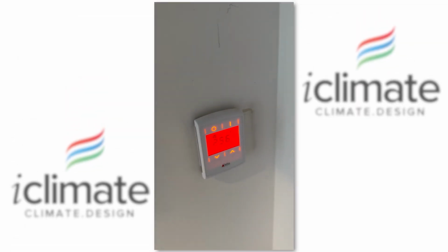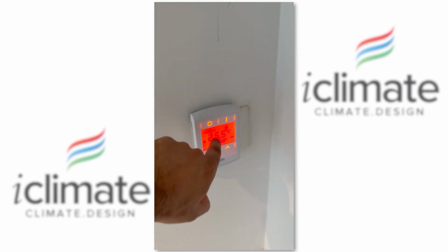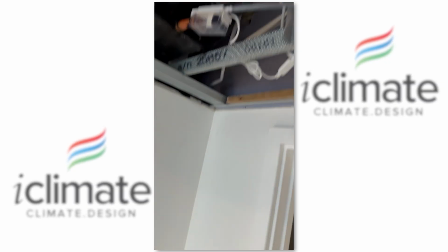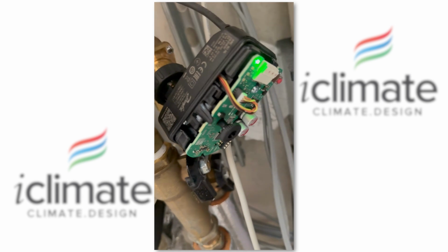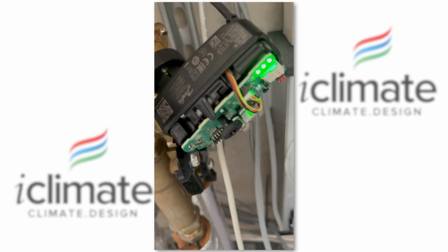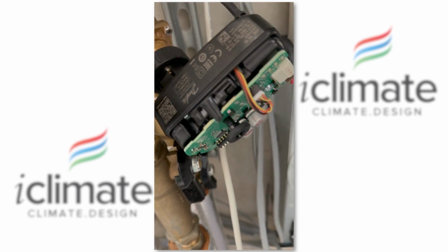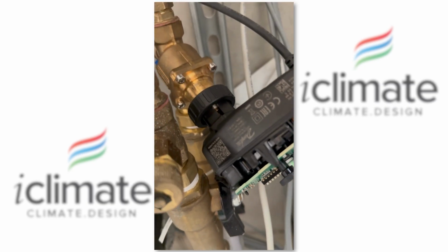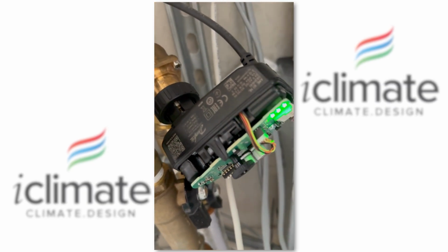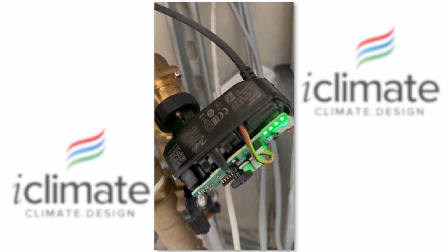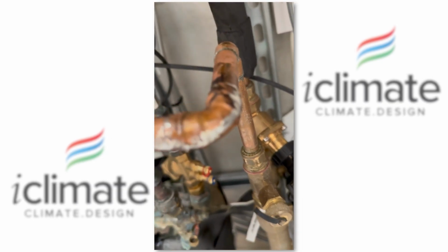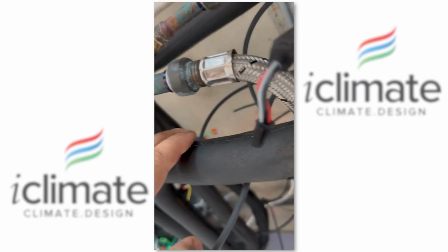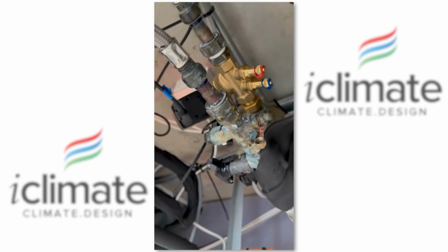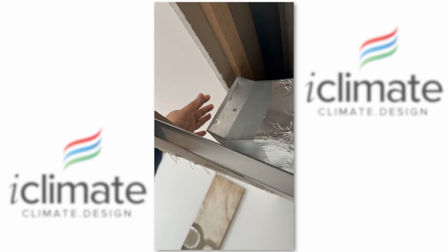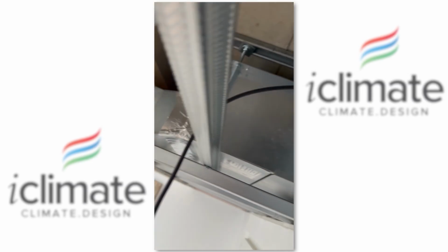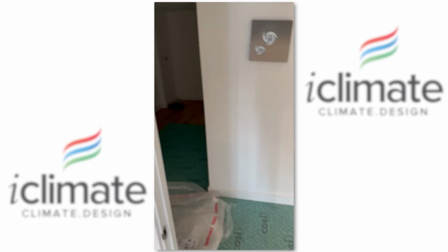When you put on heating, our Delta goes into red. 28 is the set point, 25.5. And we are seeing the heating valve on the right side, the actuator winding its way down through the PICV, allowing the return to open up. And we have lovely boiling hot water flow here into the fan coil unit. And we are heating on the air off. Let's go check the flow meter.